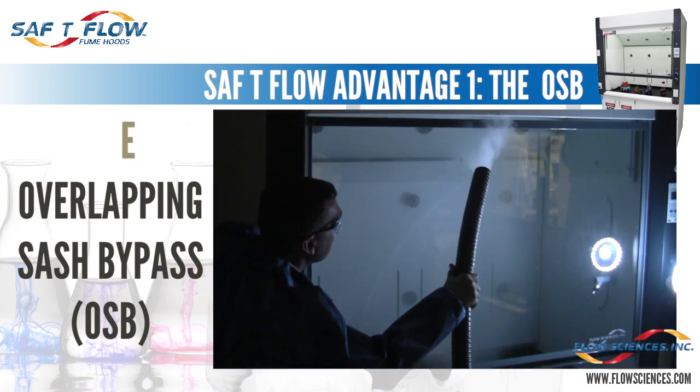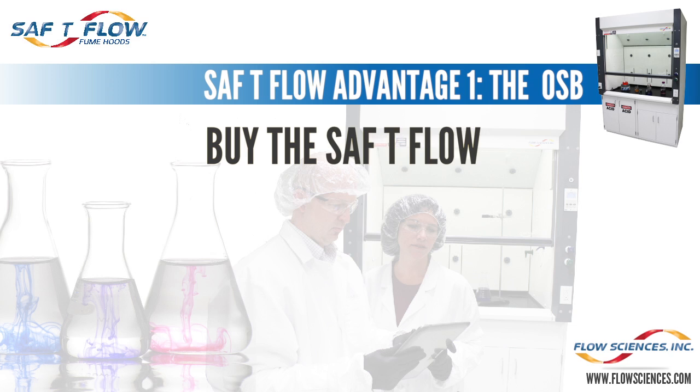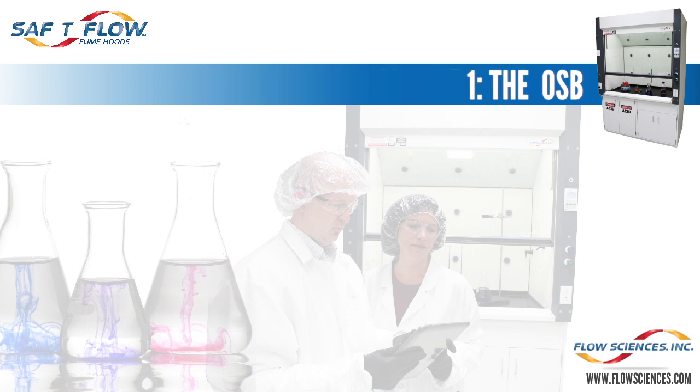The bypass is not any different. Therefore, if a building changes its exhaust strategy, no modification is needed inside the fume hood bypass structure to make the hood work under the new rules. So if your facility needs hoods now but is updating the lab extract system later, the Saf T Flow hood will not have to be refit with a new bypass system when the upgrades are installed. This is a great advantage in low-cost adaptability.